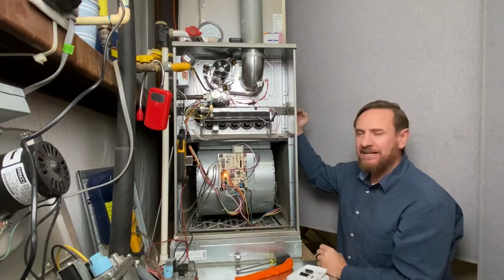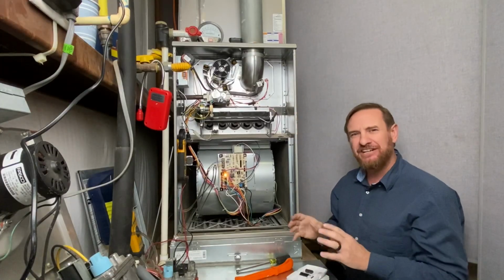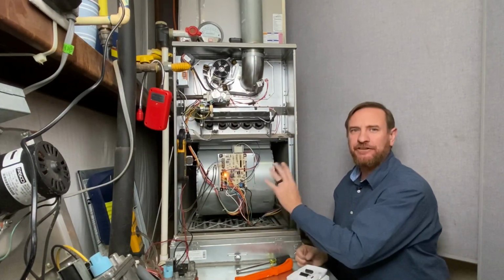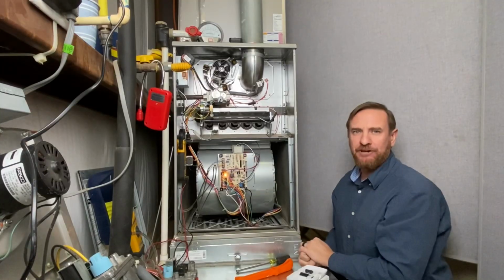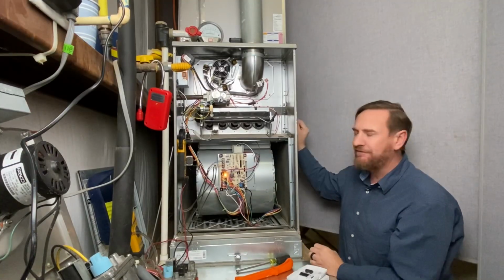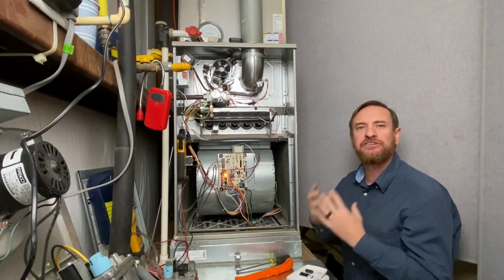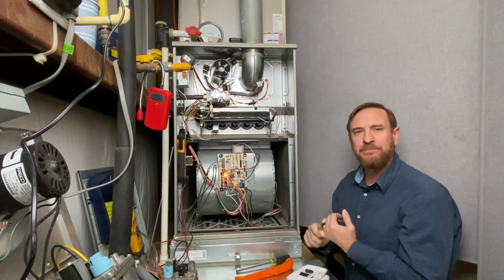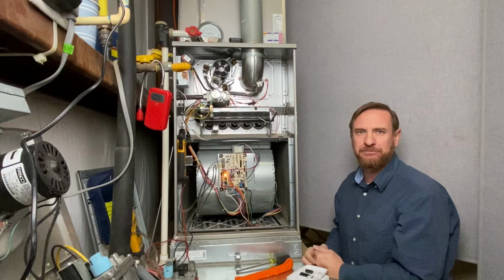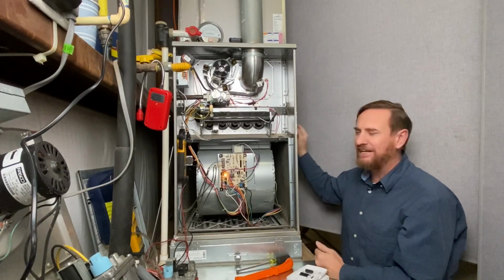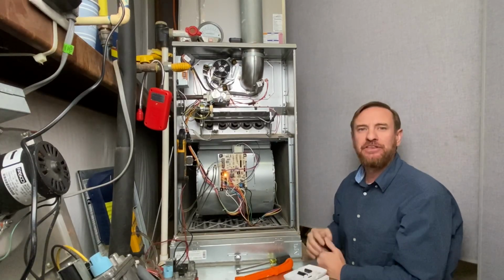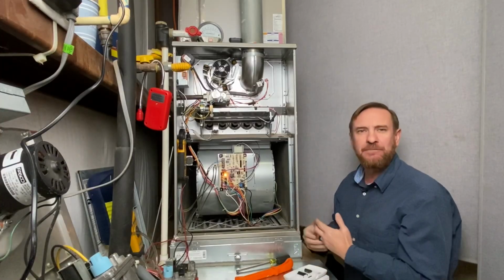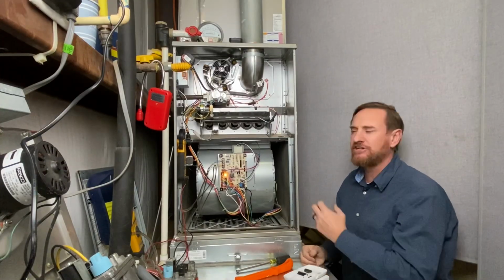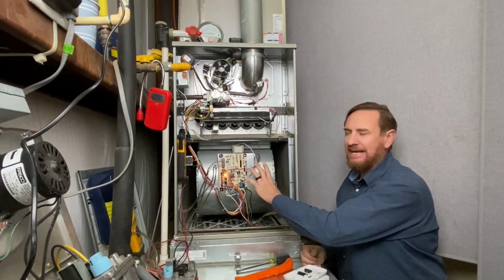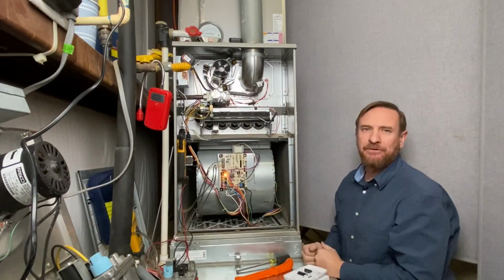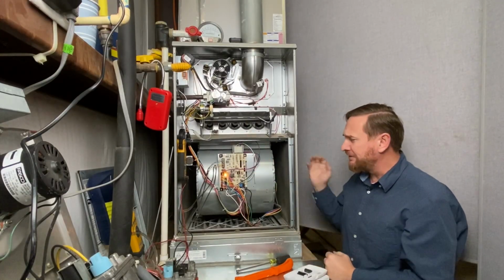So when the flames hit and it starts heating up that heat exchanger, the engineers have designed exactly how much time it needs for their furnace before they send that blower on. And that's important because when these flames heat up that heat exchanger, it needs to get to a certain temperature at a certain speed so that it has complete combustion or nearest complete combustion as possible. If this heat exchanger is too cool when those flames heat up, you're going to have an issue with smog, carbon monoxide, soot building up inside the heat exchanger. So they've designed that on delay, how long it takes between the flames and that blower coming on, as a set time. So this thing's about to cycle off.